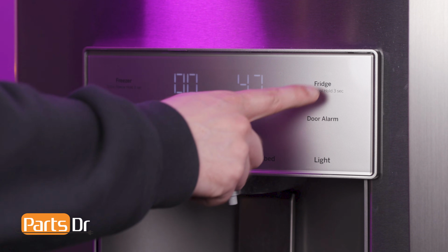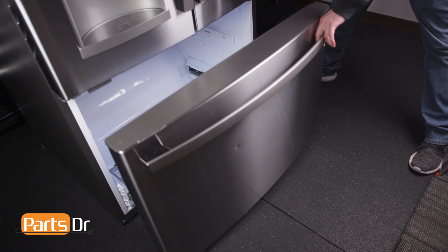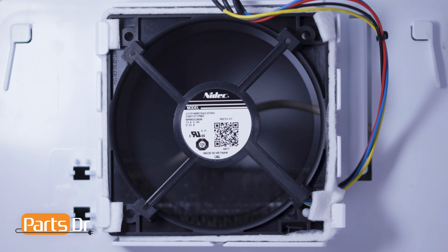Next, let's run test number 48. This test will turn on the freezer evaporator fan motor to help assist troubleshooting the fan motor system. Now, with the door open, we should be able to hear the fan motor running.